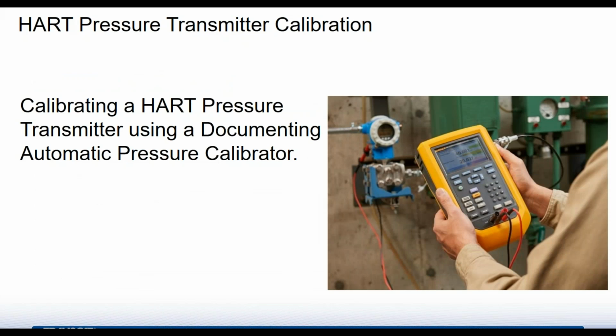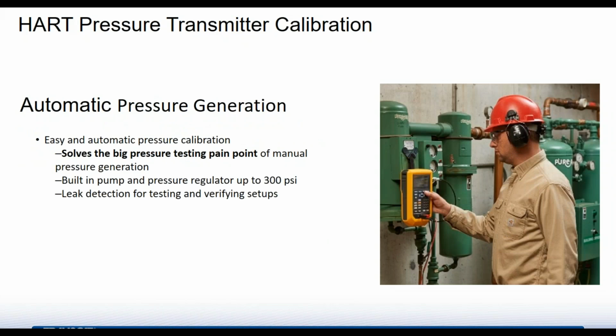Now let's talk about calibrating a HART pressure transmitter using a documenting automatic pressure calibrator. So some key advantages of having an automatic pressure generating system: it's easy to use, obviously. It's got a built-in pump and a pressure regulator. In this case, with the Fluke 729, it goes up to 300 psi. It's got built-in leak detection for verifying setups before you even start your calibration. And basically what it does is solve a big pressure pain point that I get calls on all the time, and that's having to do a manual pressure generation to do a calibration.